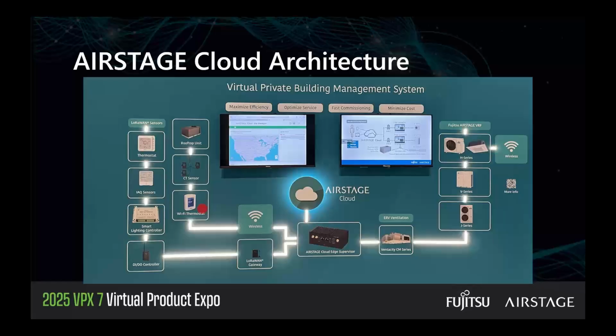Notice I said we are connecting by Wi-Fi. Though AIRSTAGE Cloud is a virtual building management system, we are not a BACnet-based system - we don't communicate through BACnet. You don't have to make BACnet connections, which is part of the appeal of AIRSTAGE Cloud. It's a simple, easy platform to use. Because of that, we try to make everything configurable and not programmable. We recognize that this system is installed and set up by contractors, and contractors by nature are not controls engineers - we don't want you to be controls engineers. So the integration is simple and straightforward using a Wi-Fi stat that manages most of that connection for you, and all you have to do is connect it to the internet.